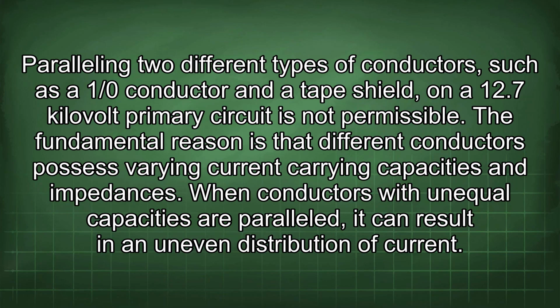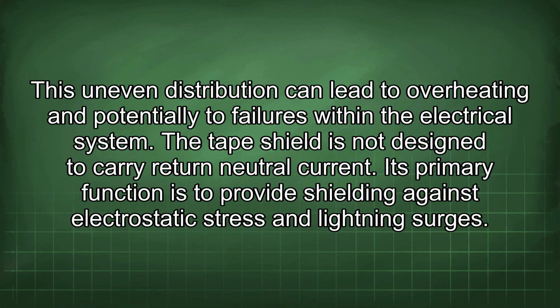Paralleling two different types of conductors, such as a 1/0 conductor and a tape shield, on a 12.7 kilovolt primary circuit is not permissible. The fundamental reason is that different conductors possess varying current carrying capacities and impedances. When conductors with unequal capacities are paralleled, it can result in an uneven distribution of current. This uneven distribution can lead to overheating and potentially to failures within the electrical system.